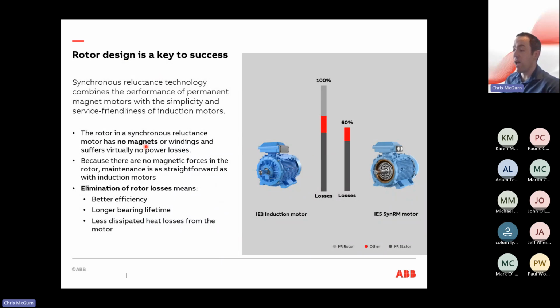Because they have no magnets in the rotor design, compared to a typical squirrel cage induction motor. It has a separate rotor design, specially made such that there is an elimination of rotor losses. The way the squirrel cage induction motor works, there is an induced current across the rotor bars themselves. That induced current causes heat, and that heat reduces efficiency. But because of the special design of the rotor in the SynRM motor, there are no rotor losses, which means better efficiency, longer bearing lifetime, and less heat losses. And that's why, again, what I said earlier about 20% less losses between each IE band. In this particular picture, you're comparing it with an IE3, so it's got 40% less losses than an IE3.